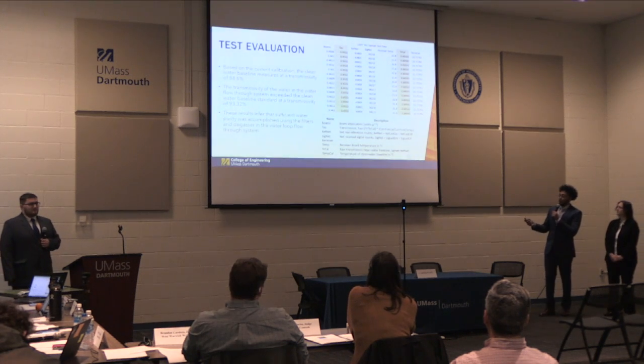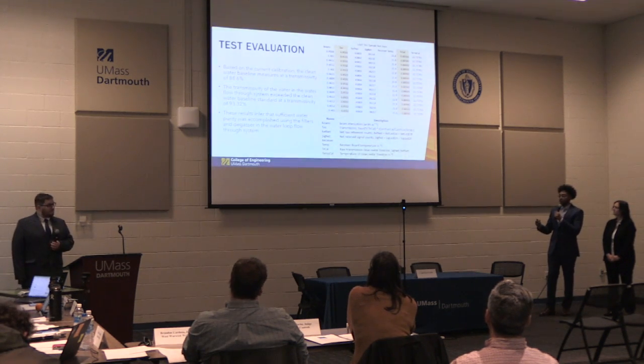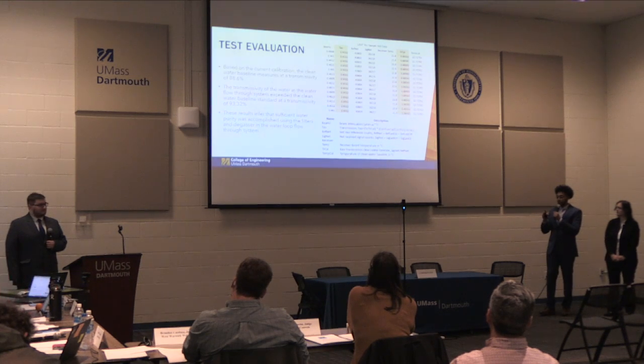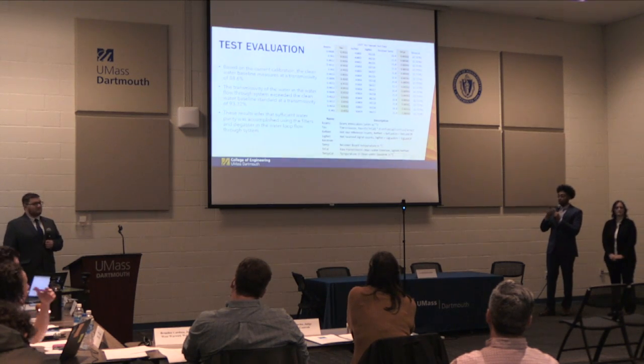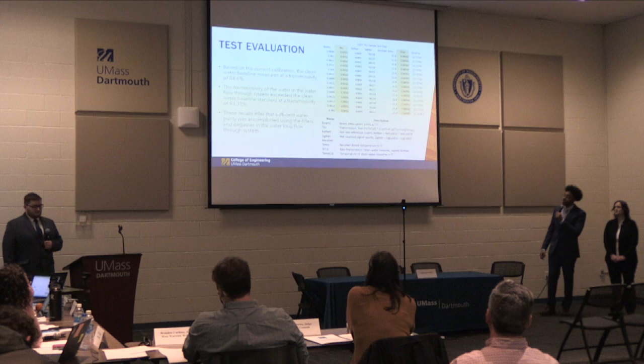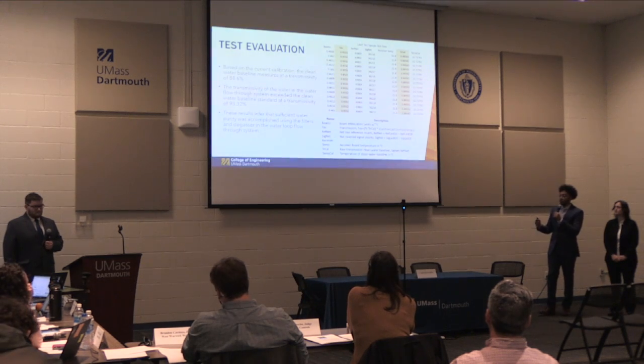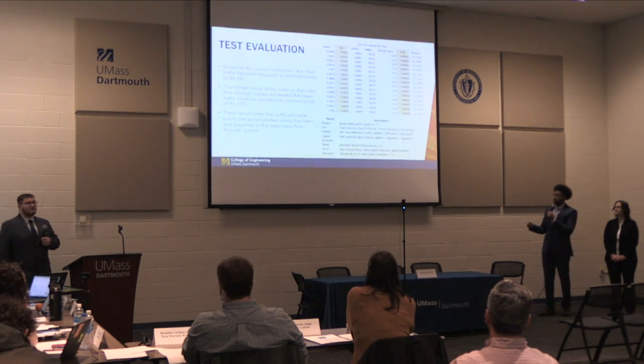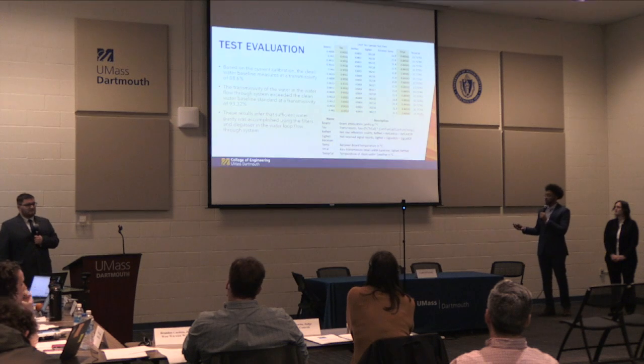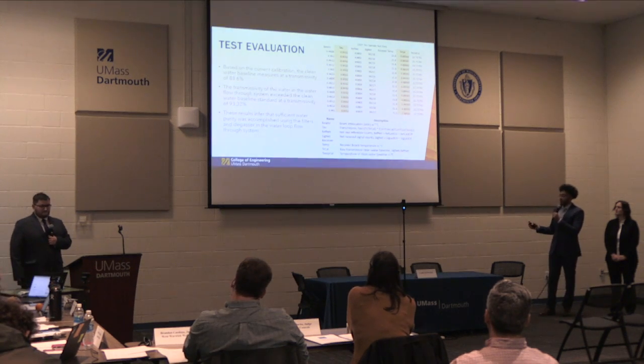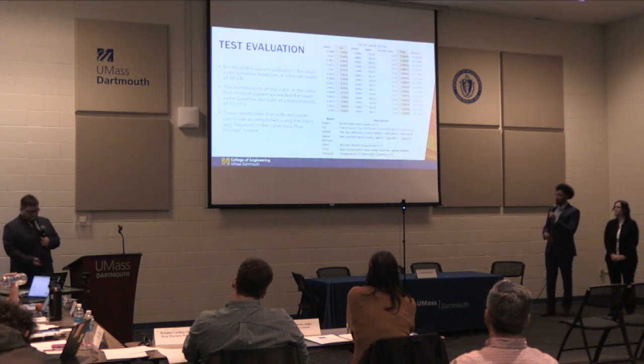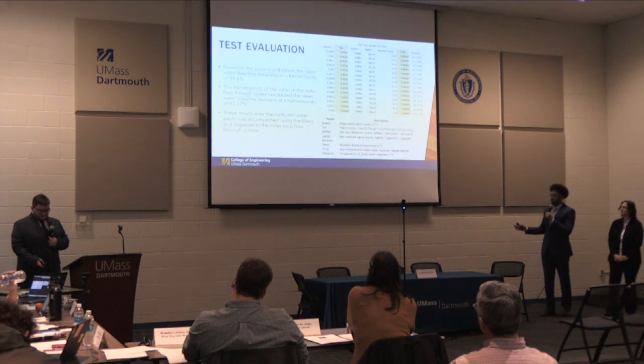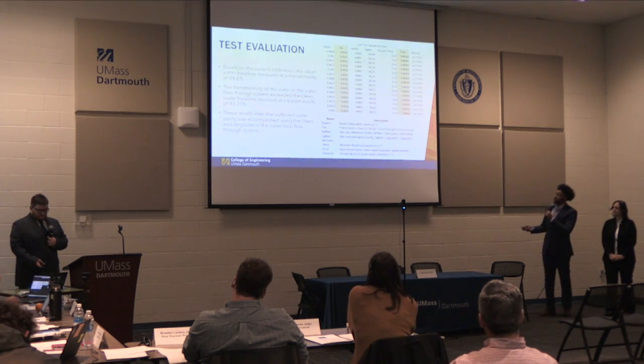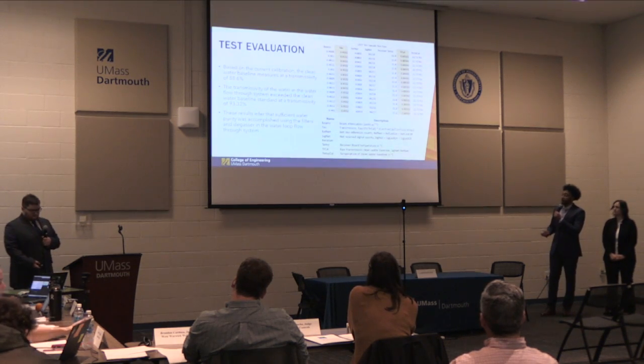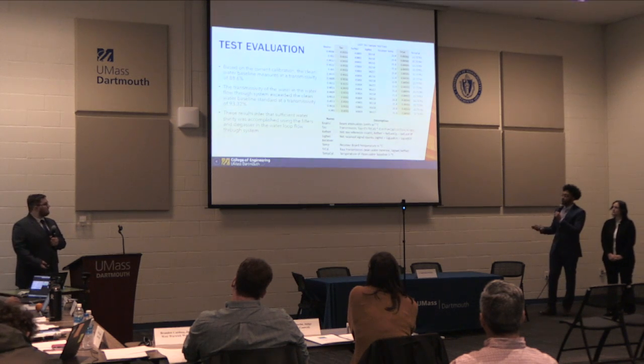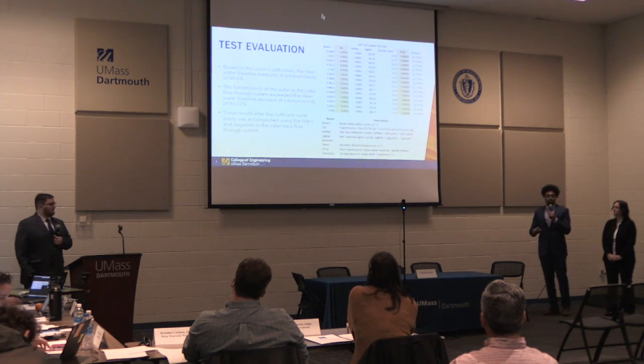These values are recorded by the sensor based on the scattering of the light beam across the lenses as it shoots through the water. The transmissivity of the water that we were able to generate going past the sensors actually exceeded the clean water baseline and generated a transmissivity of 93.32%. These results were averaged over a range of 500 data points, but these are a small subset of the data we were looking into. So I'd say these results infer that sufficient water purity was created using the process we developed.